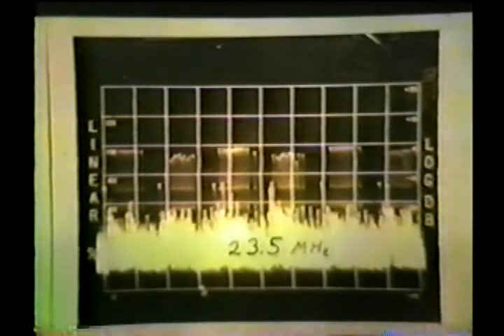To show you one of the various types of EMI, this one is called microsparking. The photograph in the upper part of the slide shows the extremely rigid pattern that's produced both on positive and negative half cycles of the power frequency. This can occur in machines at very discrete frequencies. For example, at 23.5 megahertz, we had a quite rigid pattern. This makes a popping sound due to microsparking, or that is discharges across very small gaps. If one would tune to, say, 22 megahertz or 25 megahertz, this pattern would be completely gone.